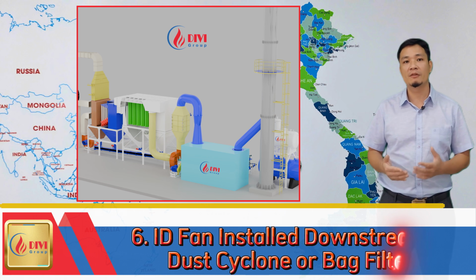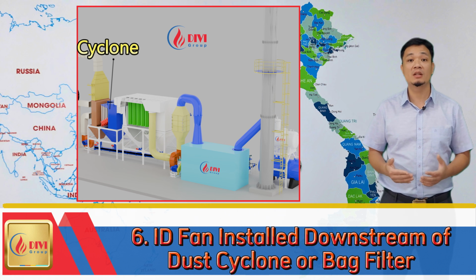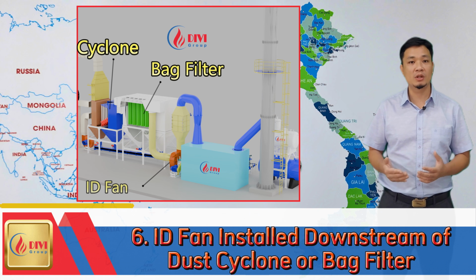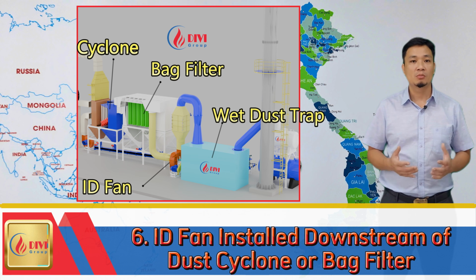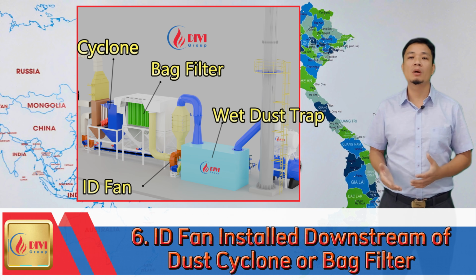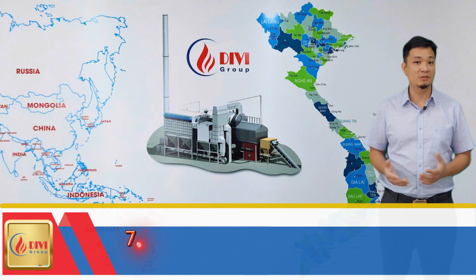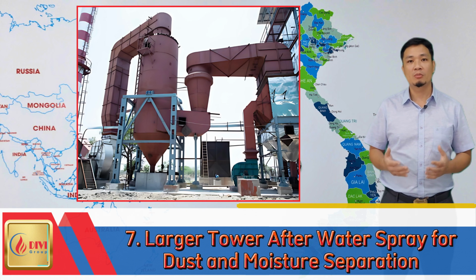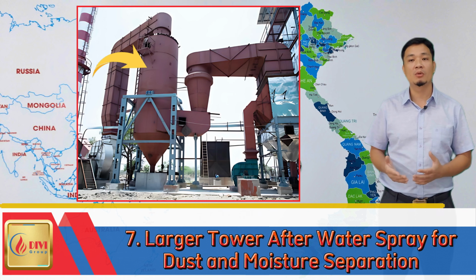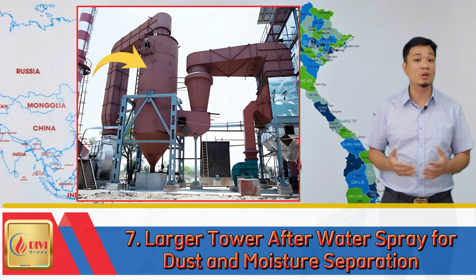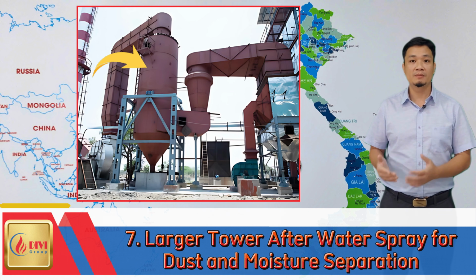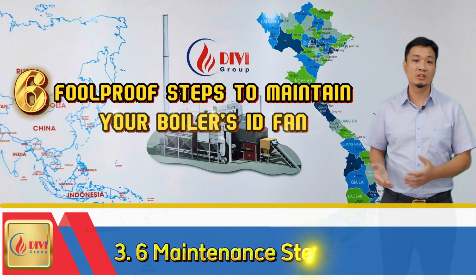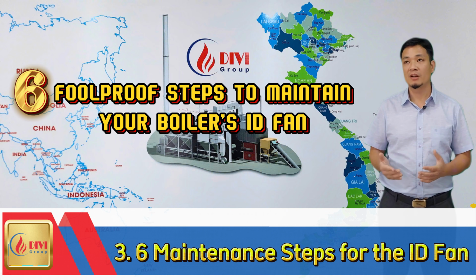6. Position the fan downstream of a cyclone dust collector or bag filter, and always upstream of a wet scrubber to prevent corrosion caused by condensed water vapor in the flue gas. 7. For fans installed after a water spray system, design a large separation tower to remove dust and water, minimizing its impact. 3. 6 perfect steps to maintain boiler-induced draft fans.